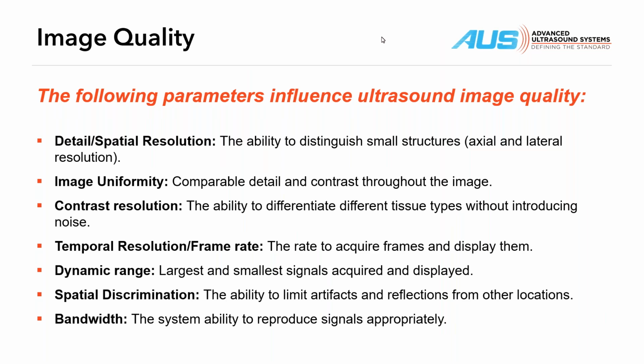A different way of saying different tissue types is different densities. Every tissue type has its own specific density, and what we're doing with contrast resolution is ensuring that the system has the ability to distinguish the different tissue densities. Temporal resolution versus frame rate. It's the rate to acquire frames and display them. This is normally measured in hertz. For example, 30 hertz, or the image is refreshed 30 times a second. So temporal resolution / frame rate. Dynamic range, largest and smallest signals acquired and displayed. Okay, largest and smallest echoes.